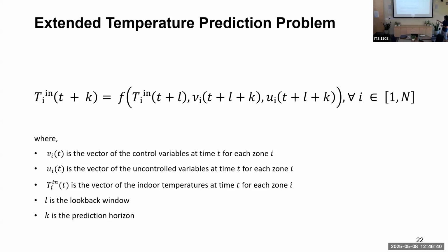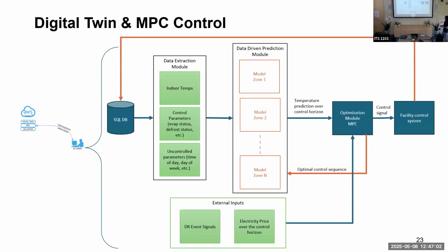How we can extend beyond just using historical data is also to use future controlled and uncontrolled inputs. So we can have a prediction for outdoor temperature, and we can have predictions for what controls you want to do at what time period. Then this problem becomes historical data plus forecasted future inputs to predict those future space temperatures. And again, this is our central module. In between, we would have a separate one for each zone, and then we can predict accurately what space temperature we result with in each zone, and then optimize our operation based on all those predictions.